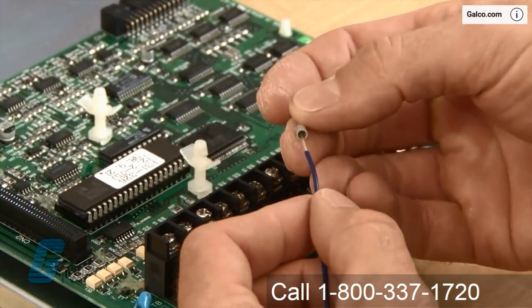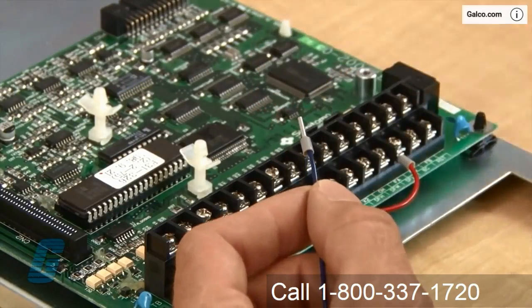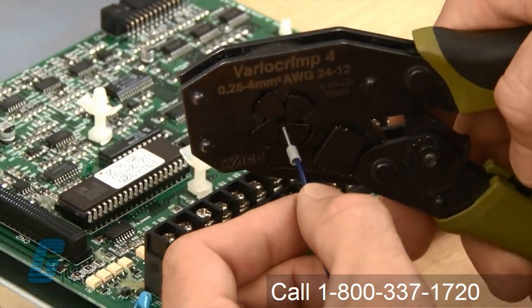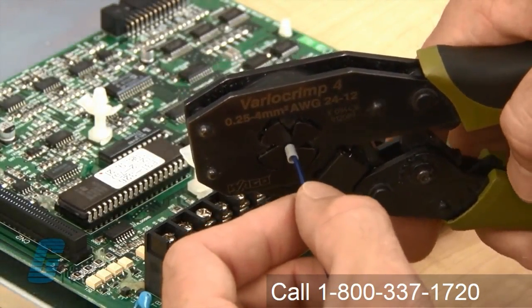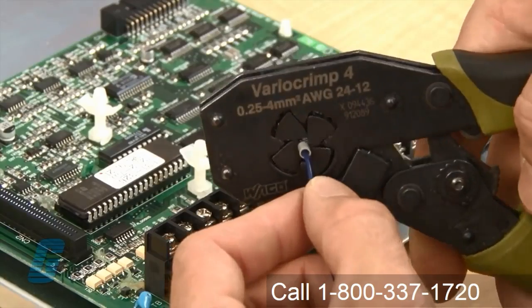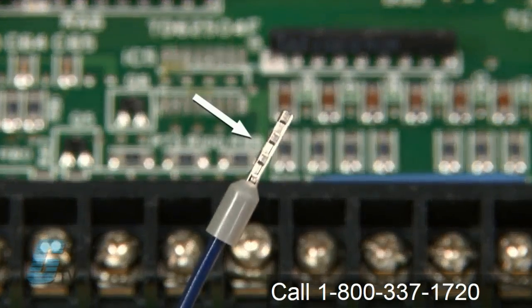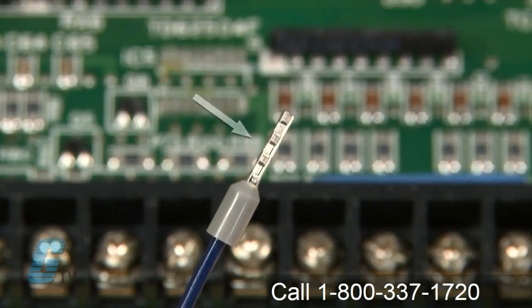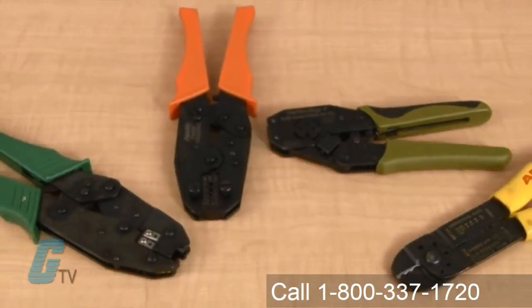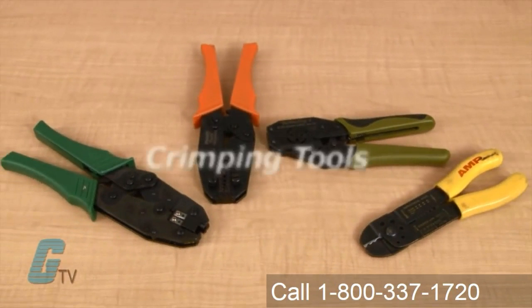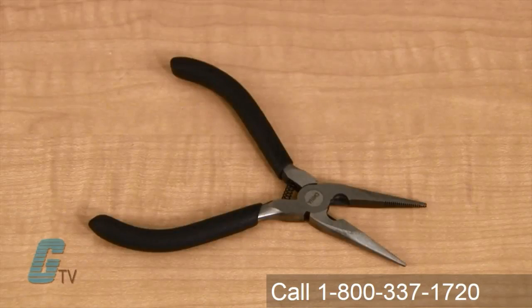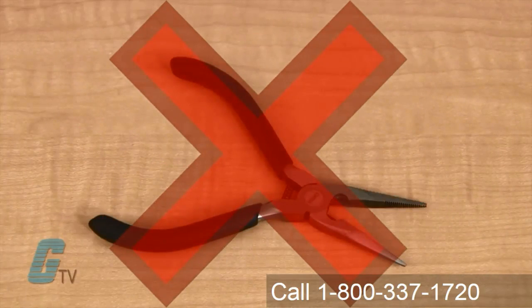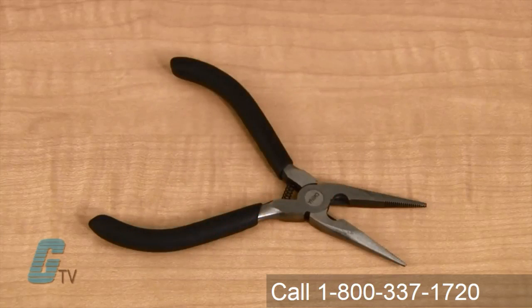Crimping means to join two pieces of metal together by deforming one or both of them to hold the other. The resulting deformity is what is known as the crimp. In order to crimp connectors onto a wire, you will need a dedicated crimping tool. Note that tools not dedicated to crimping, such as pliers, should not be used as they will not create the proper cold weld that a crimping-specific tool will.